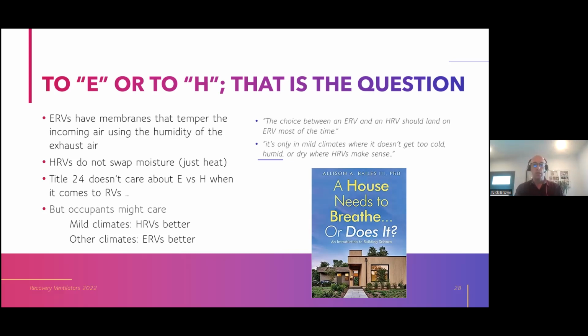And he said the choice between ERV and HRV should land on ERV most of the time. He's in Atlanta, so he's got a lot more humidity to deal with than we do out here. But he said it's only in mild climates, not too cold, not too hot, not too humid or dry, where HRVs make sense. So I think this is something for you and your HVAC and your sub and your client to evaluate, the particular climate you're planning to install in, and make an informed decision, maybe consult your manufacturers. But I put an HRV in the main house and an ERV in the ADU, and I don't see appreciable difference in how they function here in climate zone 6, a couple of miles from the coast.